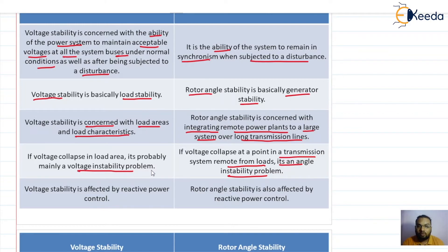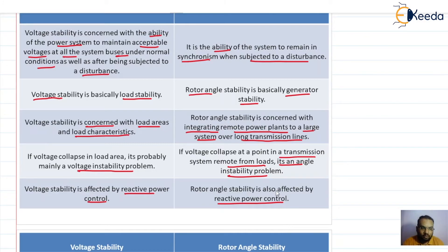The key difference between voltage instability and rotor angle instability: voltage stability is affected by reactive power control. Rotor angle stability is also affected by reactive power control, but it can also be discussed in terms of real power control. More specifically, voltage stability is mainly affected by reactive power control only, whereas rotor angle stability can be controlled with the help of both real power and reactive power control.